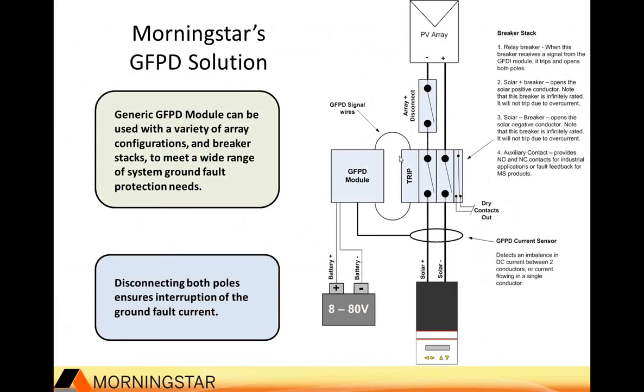What Morningstar does is instead of predicting that the current will flow through that breaker or fuse, we actually are monitoring the current through the entire system. Okay, we have a current sensor here, and this works very similar to the way an AC-based ground fault protection device, such as those outlets in bathrooms, are designed to work. They monitor current, and if there is an equal flow, as there should be, what goes out comes back, then your system is fine. If there is an imbalance detected using this current measurement device, that imbalance indicates that current is being lost somewhere. We don't necessarily know where, but it's not returning the way it should. Therefore, there's a ground fault, and the system is shut down.